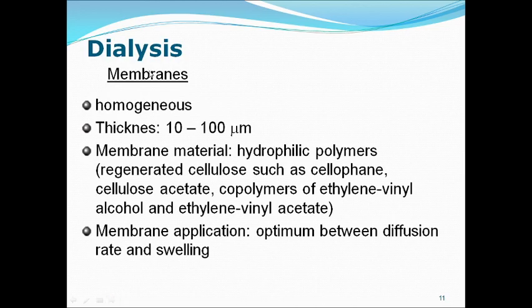Dialysis membrane features: the membrane is homogeneous, with thickness around 10 to 100 micrometers. Membrane materials include cellophane, cellulose, cellulose acetate, and copolymers of ethylene vinyl alcohol and ethylene vinyl acetate. The membrane application requires an optimum balance between diffusion rate and swelling. You can take any other materials — if they are better than these, you can select them as membrane materials.